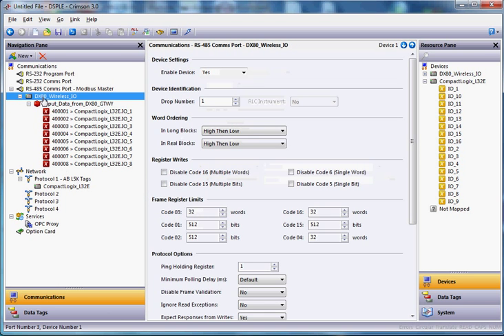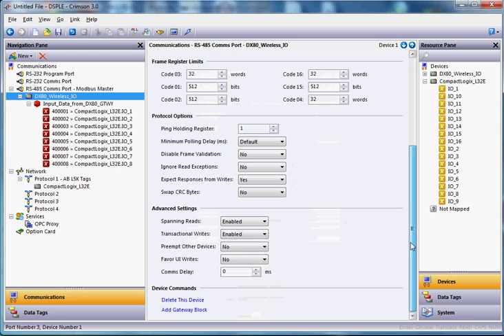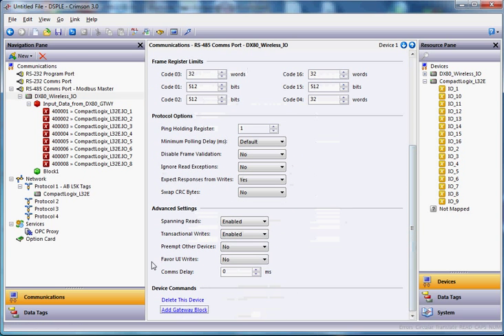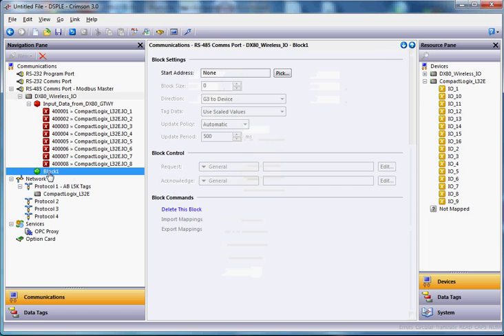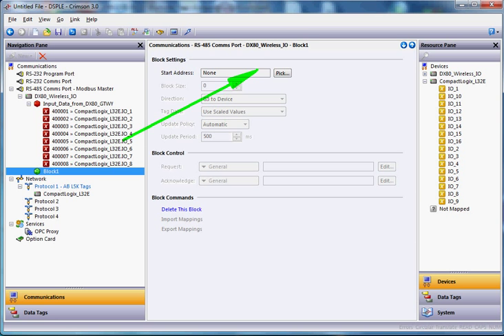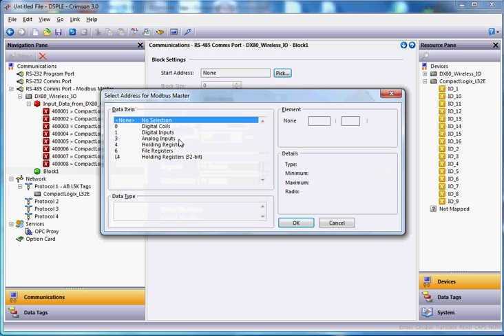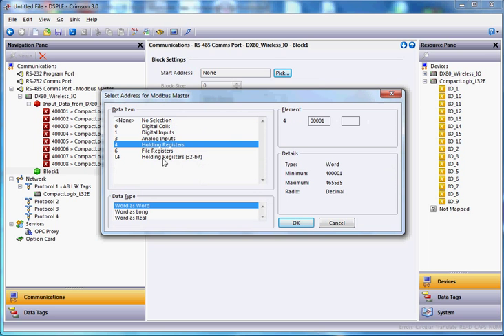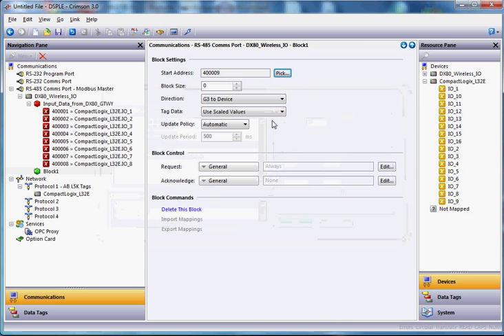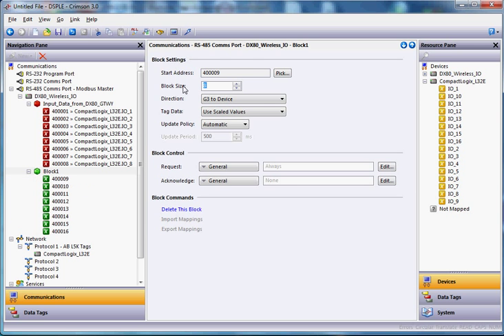So I will click right here, back up on the DX80 gateway. And I'll slide down and I'll add another gateway block right here. And then I'll highlight this block. And this one, I want it to start at 40,009. Because if you look, here's 40,008 right there. So if I hit the Pick button right here, click on the holding registers. Not the 32-bit, but the regular holding registers. And right here, put in number nine this time, enter. Once again, it's going to be a block size of eight. So I'll put an eight right there.